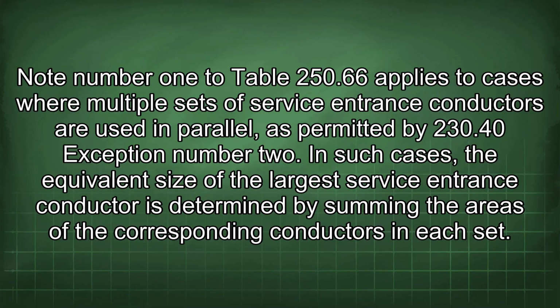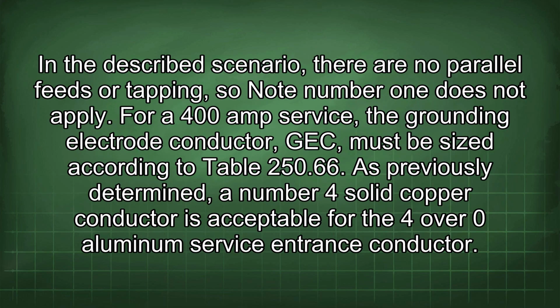Note number 1 to Table 250.66 applies to cases where multiple sets of service entrance conductors are used in parallel, as permitted by 230.40 exception number 2. In such cases, the equivalent size of the largest service entrance conductor is determined by summing the areas of the corresponding conductors in each set. In the described scenario, there are no parallel feeds or tapping, so note number 1 does not apply.